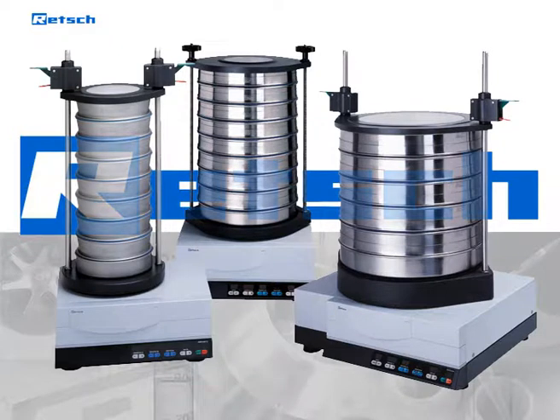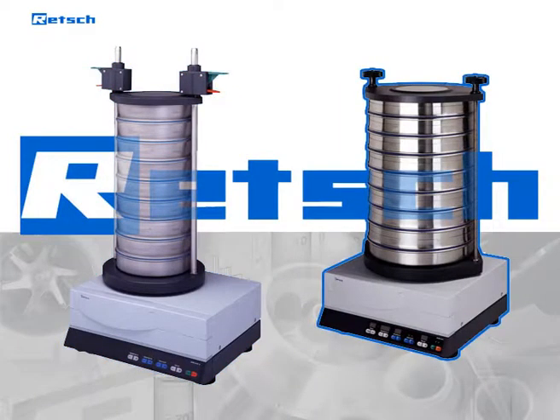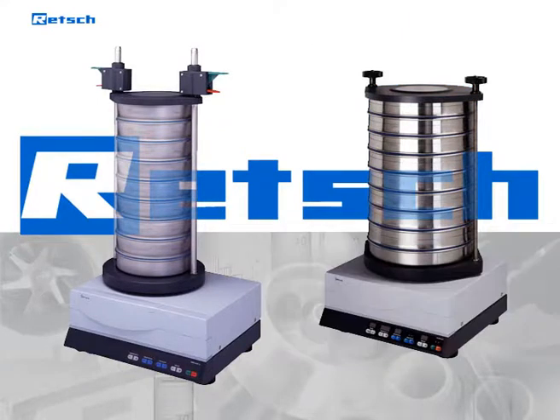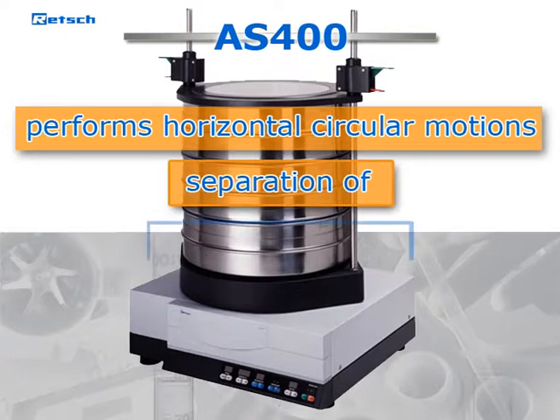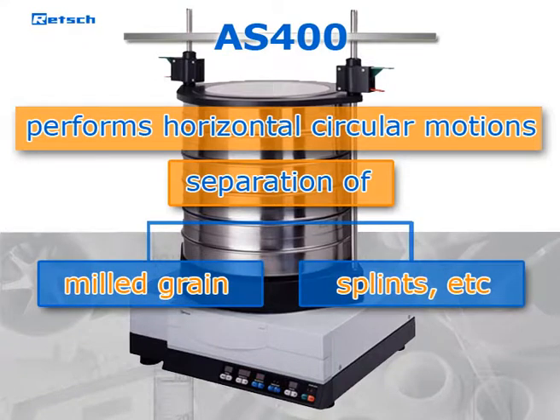Retsch sieve shakers are available in different models to support the various needs of customers. All sieve shakers of the AS200 and AS300 series work with a drive that produces a 3D throwing motion. The AS300 provides a two times larger sieving surface and handles heavier sieve stacks of up to 10 kg. The AS400 performs horizontal circular motions, which is particularly suitable for the separation of products such as milled grain, splints, and similar materials, and is also required for testing plastics.